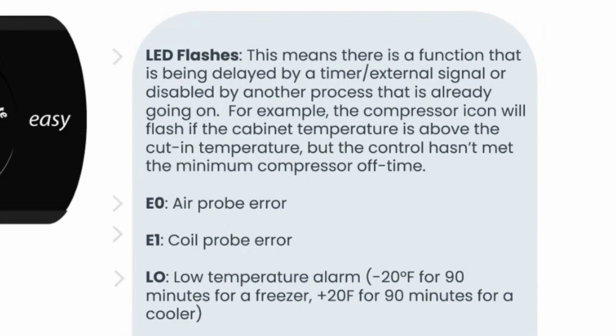As far as the LED flashes go, again, it's kind of like the ED error. It doesn't necessarily mean that there's a problem with the unit. It just means that there's a function that hasn't been able to begin yet because something else hasn't wrapped up. So the example that we normally use is the compressor off time, the minimum off time. You have a cooler, it's set at 33 degrees, the unit satisfies. The second it satisfies, Bud comes in, opens the door, and a rush of hot air comes in there, and the temperature inside that cabinet goes up to 48 degrees, let's say. Well, at that point, we still haven't met that minimum compressor off time because it's only been, let's say, 20, 30 seconds. So the unit has to wait for that minimum compressor off time to be met, which is usually 2 minutes. And then once that 2 minutes is up, the unit can begin into its cooling mode.